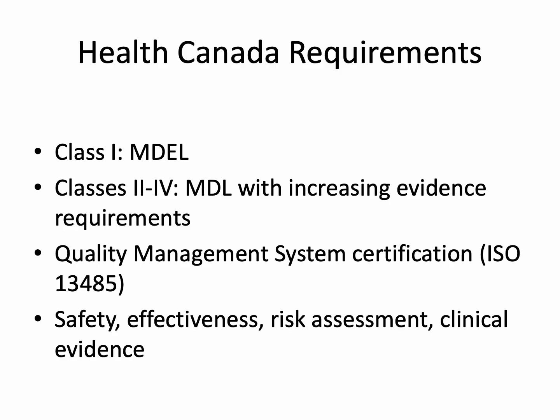Key evidence requirements include ISO 13485 Quality Management System certification, safety and effectiveness data, risk assessment documentation, and clinical evidence for higher-risk devices. A clear understanding of these requirements allows manufacturers to design studies and compile evidence that satisfies Health Canada while coordinating submissions with other jurisdictions.